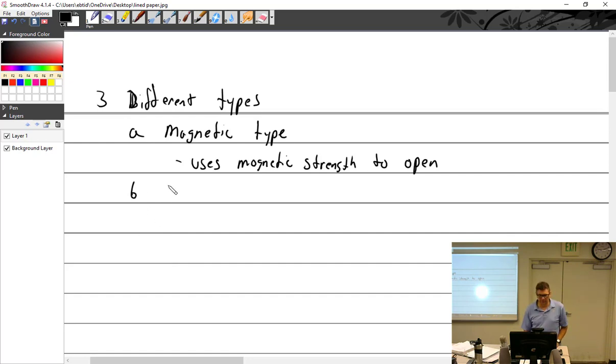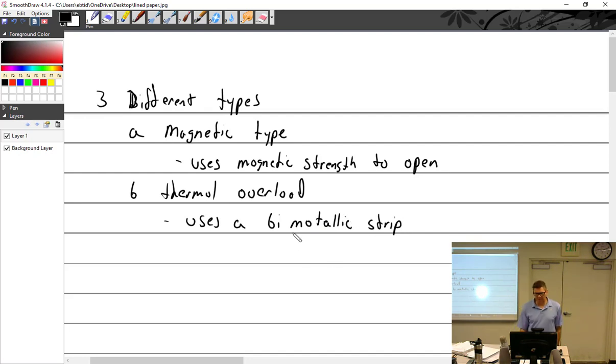There's the thermal overload type, which uses a bimetallic strip. As the name implies, bimetallic means it's made out of two different metals fused together. When heat goes through it, they expand at a different rate, so they bend—and when they bend, that's the tripping action because they got hot. So it uses a bimetallic strip, which bends when heated, and trips.